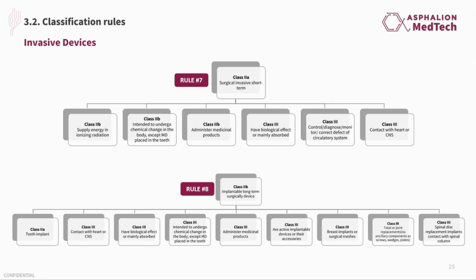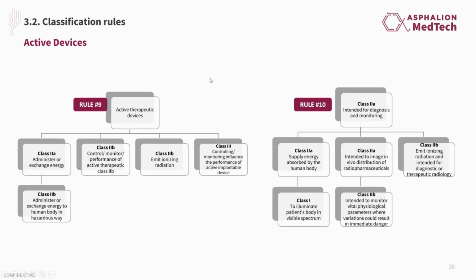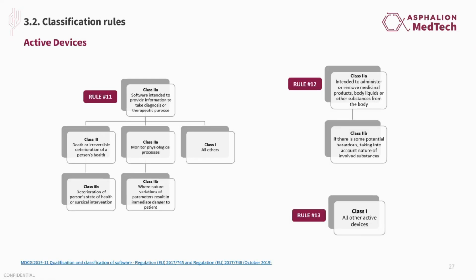then we have also these two rules applicable to invasive devices. Rule 7 is for short-term surgical invasive devices. This is devices whose duration of use is between 60 minutes and 30 days. And Rule 8 is applicable to implantable and long-term surgical invasive devices. Okay, we go further with the next group, and rules 9 to 13 are applicable to active devices. For example, Rule 9 applies to active therapeutic devices. Rule 10 is for devices for diagnosis and monitoring. And then we have Rule 11, which is for software. If your device is intended to administer and or remove medicinal products, then Rule 12 applies to your device, and Rule 13 applies to the rest of active devices.